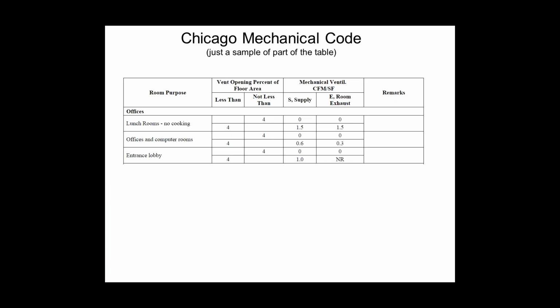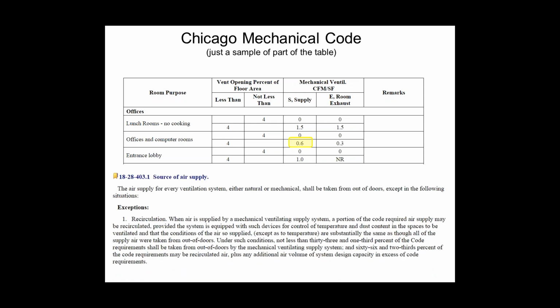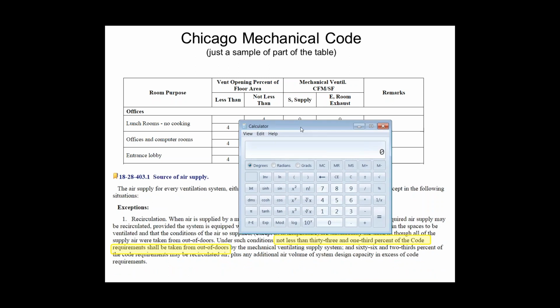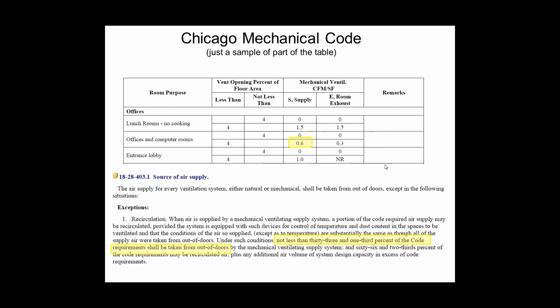City of Chicago does not tell you how much outside air to bring into particular spaces. It tells you how much supply air to bring into particular spaces. And for that same office example we were just looking at, it says bring in 0.6 CFM of supply air into that space, even if that space doesn't need that much CFM to cool it. That's what you've got to design it for. And then in a different section of the code, it specifically says whatever supply air you bring to the space, at least 33 1/3% of that has to come from outside, right? So for the case of an office building, if we pull up our little calculator and say 0.6 times 0.33, I've got to bring in 0.2 CFM per square foot of outside air into an office building in the city of Chicago. 0.2 is a pretty high number.